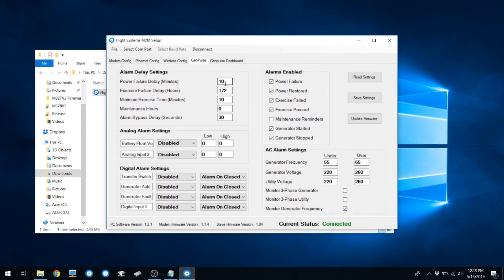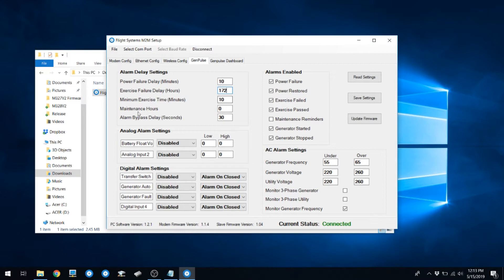You can set up your power failure delays, your exercise failure delay, and your minimum exercise time. Make sure you set your minimum exercise time to something a little less than what your generator exercises for. If you don't, the GenPulse will never think that your generator exercised properly.